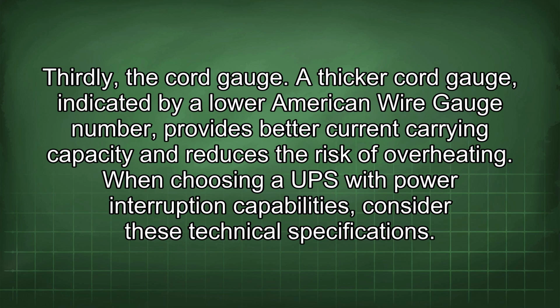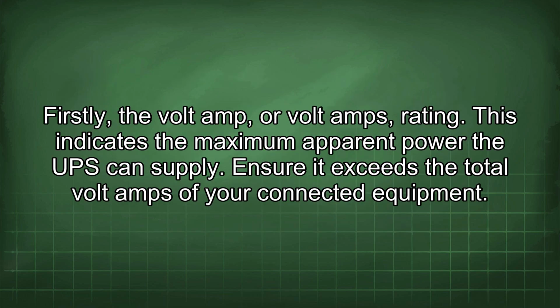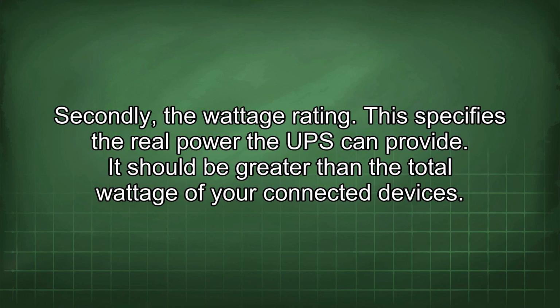When choosing a UPS with power interruption capabilities, consider these technical specifications. Firstly, the volt-amp, or VA, rating. This indicates the maximum apparent power the UPS can supply. Ensure it exceeds the total volt-amps of your connected equipment. Secondly, the wattage rating. This specifies the real power the UPS can provide. It should be greater than the total wattage of your connected devices.